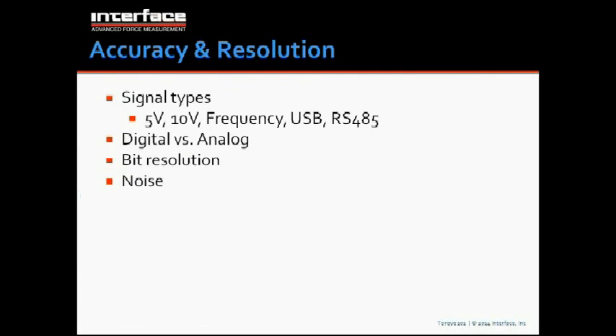Different signal types: 5 volts, 10 volts. A lot of the sensors are available with either 5 or 10 volts. People ask, well, which one is better? Well, it really matters just to match the output of the sensor to the input range of your data acquisition system. So if you have a 10-volt input range, you should select a 10-volt output from the sensor. But it's not necessarily better or worse. It just matches. And then frequency: if you have the ability to measure frequency on your data acquisition, the frequency output can be desirable.